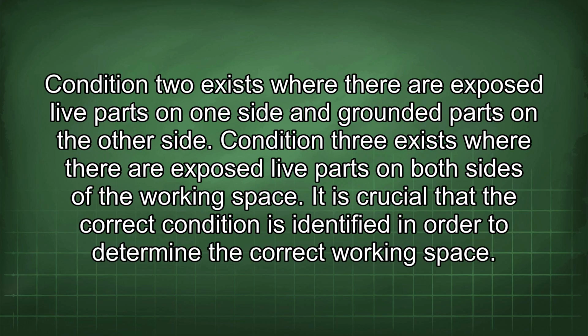This could be a concrete wall, for example. Condition 2 exists where there are exposed live parts on one side and grounded parts on the other side. Condition 3 exists where there are exposed live parts on both sides of the working space. It is crucial that the correct condition is identified in order to determine the correct working space.